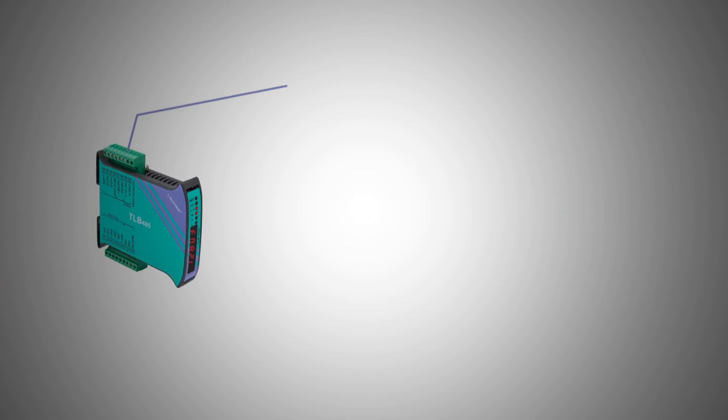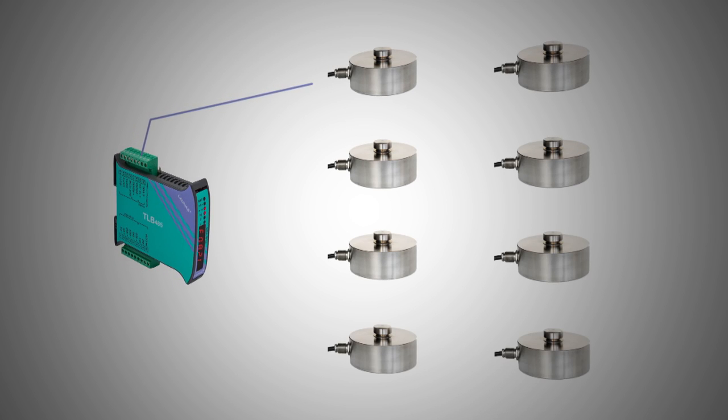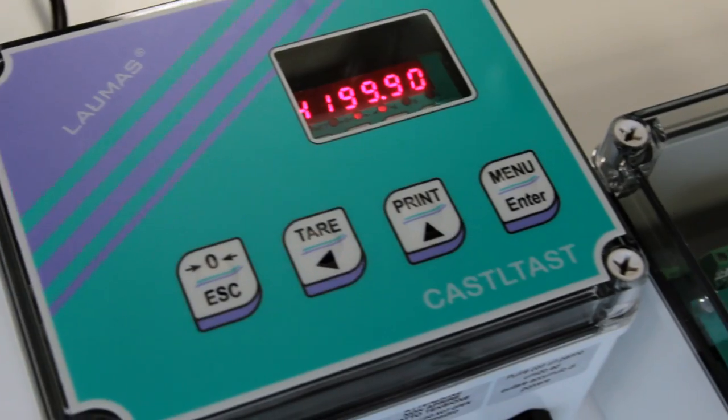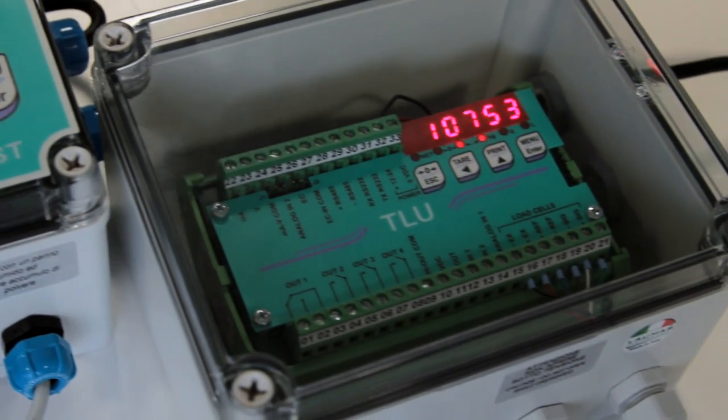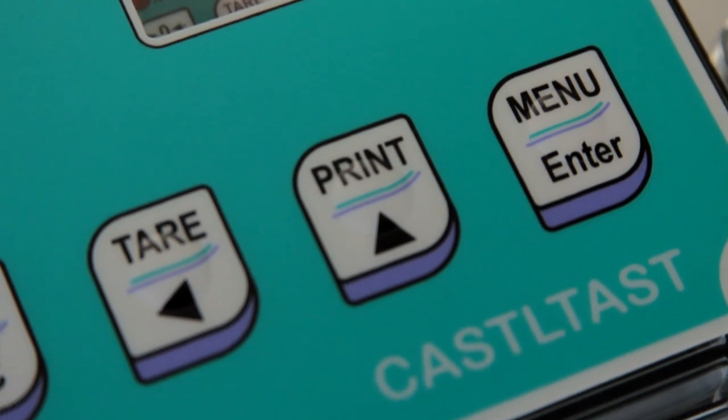Laumas weight transmitters are able to support up to 8 load cells in parallel and are fitted with an integrated RS-232-485 serial output and optionally, alibi memory. The IP67 box and 8X IP67 versions are specially designed for field installation and therefore avoid the need for a junction box.